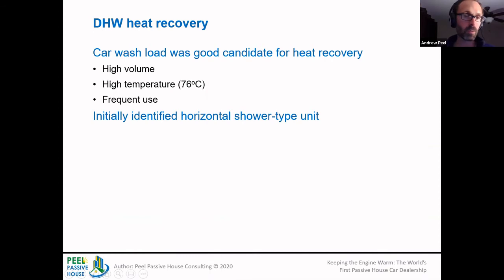Now, for anyone who's worked with drain water heat recovery devices, you have a vertical pipe you install below the bathroom, and the wastewater drops into the vertical unit, and then the cold water comes and recovers heat from that through the pipe and gets fed to the shower. There actually exist horizontal versions of that that you can install under showers. They're not quite as efficient, but they still work well.